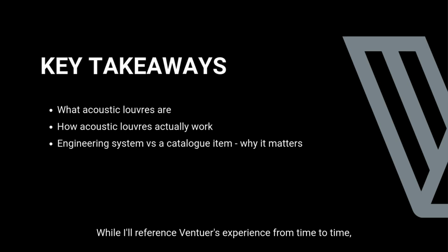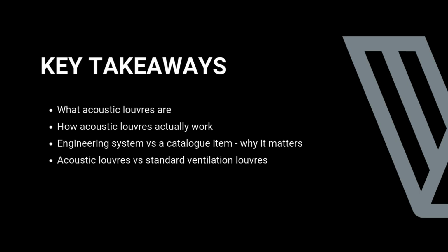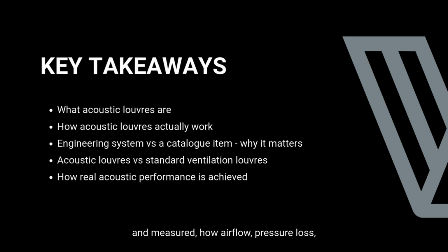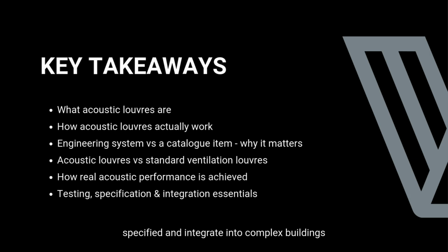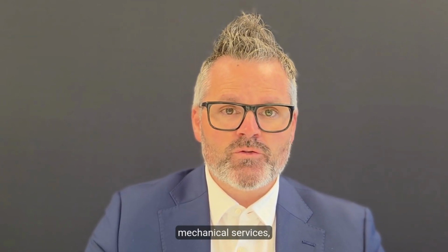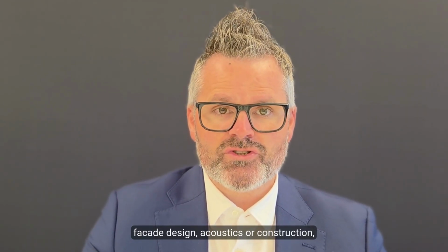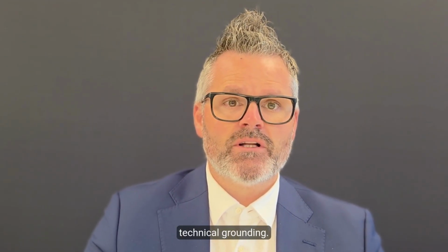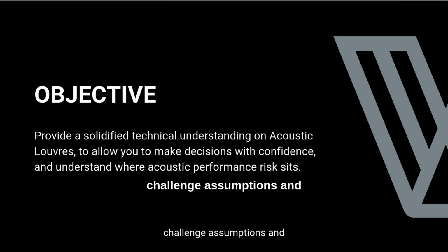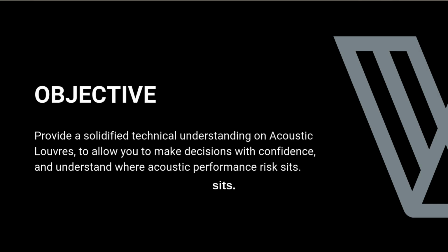While I'll reference Ventuer's experience from time to time, this session is fundamentally about giving you a clear practical understanding of what differentiates an acoustic louver from a standard ventilation louver, how acoustic performance is achieved and measured, how airflow, pressure loss, weather performance, and structure interact with acoustics, and how acoustic louvers are tested, specified, and integrate into complex buildings. If you work in architecture, mechanical services, facade design, acoustics, or construction, this session is intended to give you a solid technical grounding, the kind that helps you make confident decisions, challenge assumptions, and understand where performance risk actually sits.